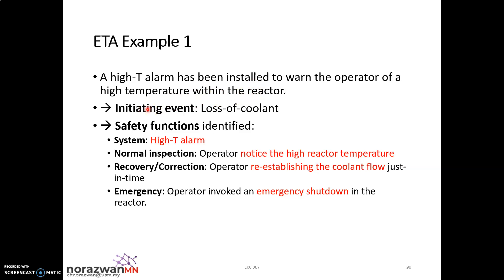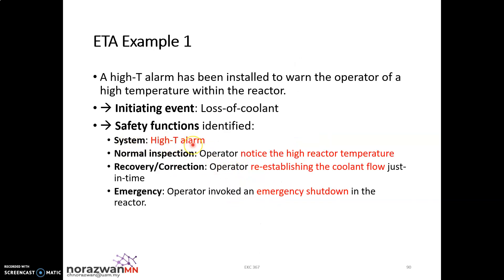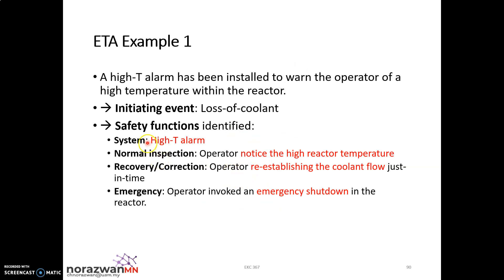After you have your initiating event, you need to identify your safety functions. The first obvious safety function is your high temperature alarm system. The second safety function involves the operator — the operator will notice the high reactor temperature by looking at the reading or at the monitoring system.